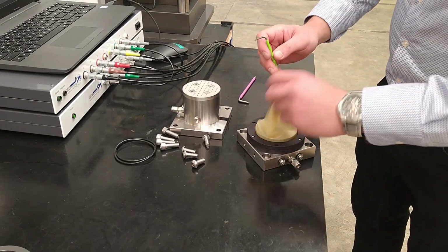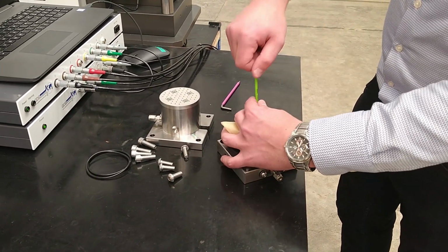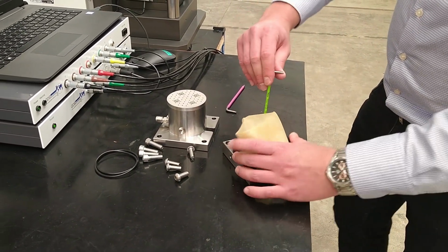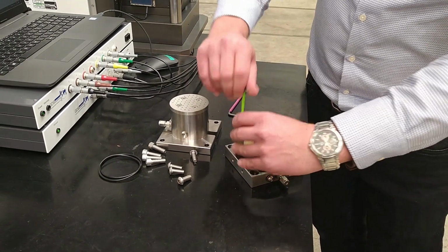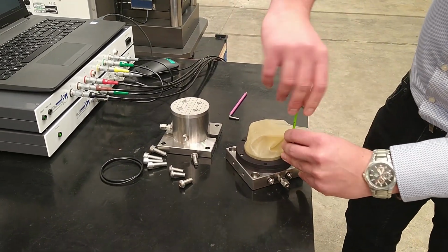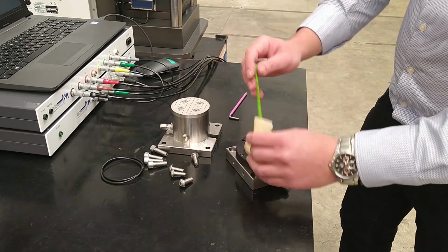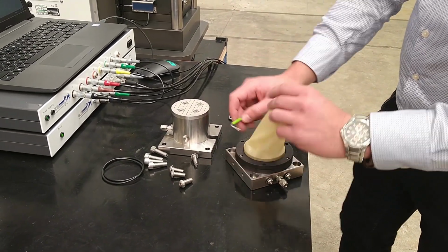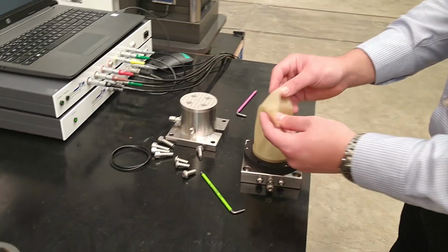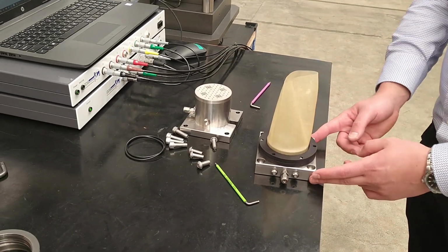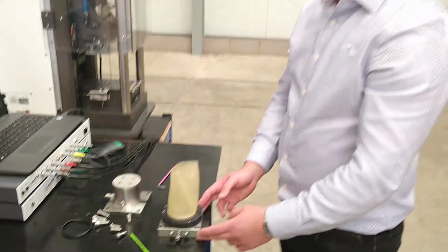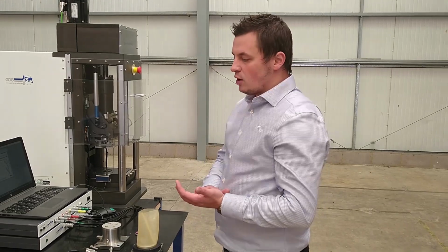The screws for both of the rings don't need to be super tight, as they're only holding the O-rings down to make sure they're compressed against the membrane and the side of the pedestal. So that would be our typical assembly for all of the types of sample preparation. For more information about different options and different hardware to prepare the sample, please refer to GDS help sheet number 146.